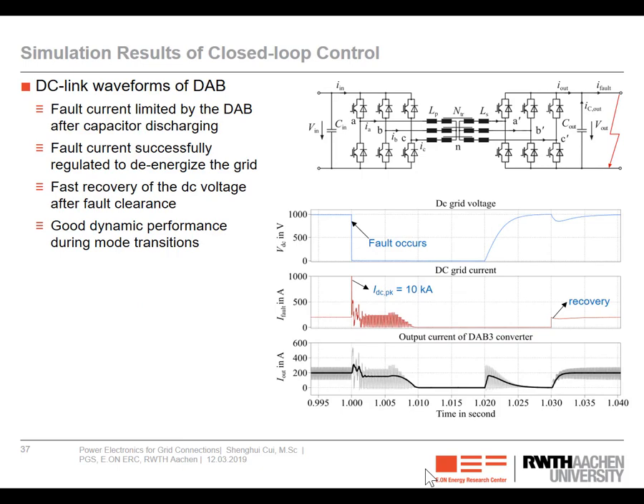So here there's a brief simulation result. In the first phase, we will see that as soon as the short circuit happens, there are immediately inrush currents, and then the DC link voltage collapses to zero. And afterwards, this converter transitions to the fault-tolerant fault ride-through mode, so that the current is decreased and regulated at a certain level for a certain time, so that the protection scheme can localize the fault area. And then the converter controls the DC link currents to zero. So we call it the fault current extinguishment.